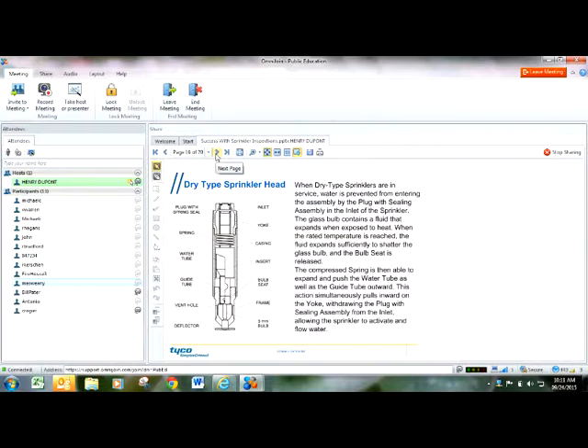The other most common sprinkler head is a dry pendant sprinkler head. This sprinkler head has a barrel manufactured onto the sprinkler head itself, and the length of this barrel is whatever you want it to be. If you have a dry pipe sprinkler system, if you think back to a few slides ago, you don't want water trapped anywhere in your system. So this head has a plug on the top of it that just threads right into the sprinkler branch line. If the head reacts to heat, the bulb breaks, the plunger comes out, and then that plug will shoot right out the bottom through the sprinkler head, allowing water to enter the sprinkler drop.